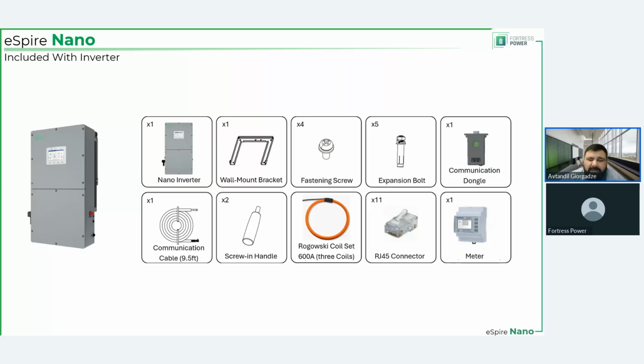And also, maybe I should mention it later. I will probably mention it later anyway, because I think I have it on one of the slides. But the CT signal cables, from where they deliver that analog output to the meter, those cables cannot be extended. So you have the CT to meter distance limited by the length of those analog cables, which we will check later together. I believe that is 4 meters, which is almost like what? However many feet. I think it's 4 meters.